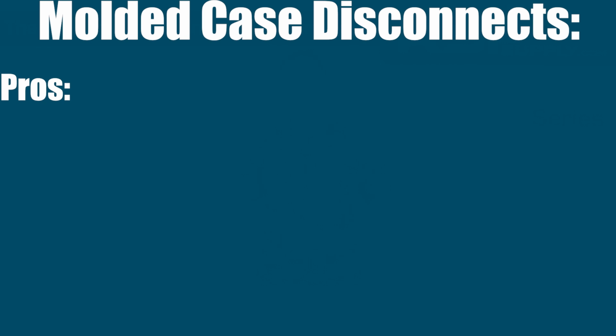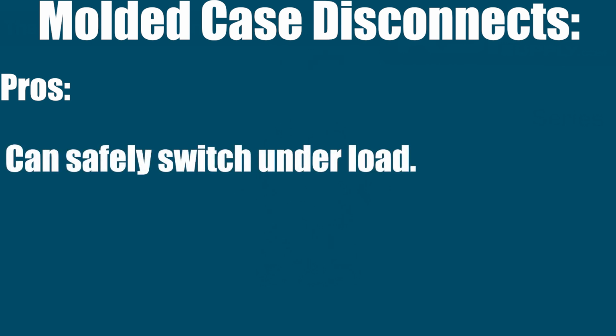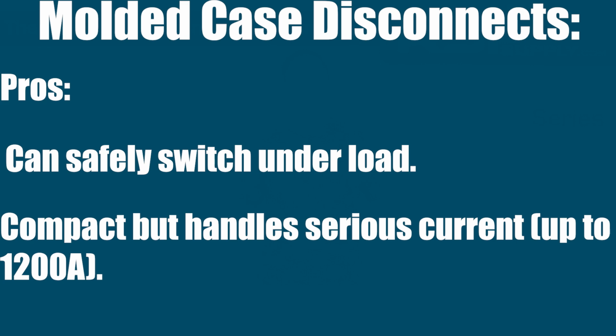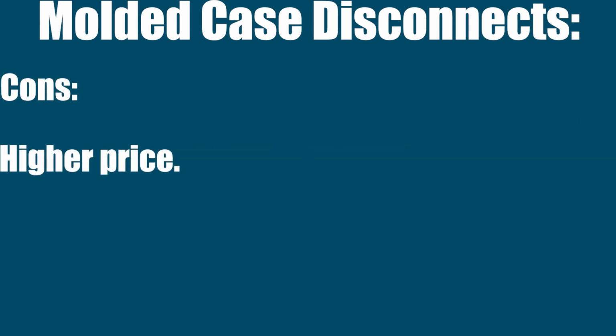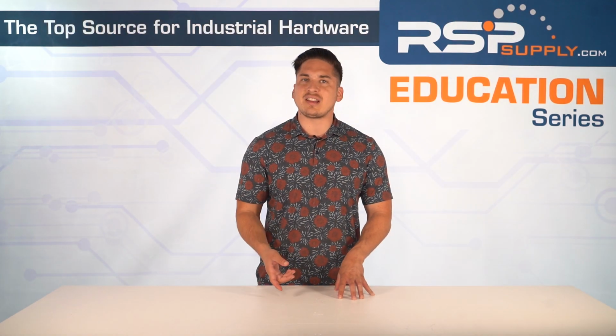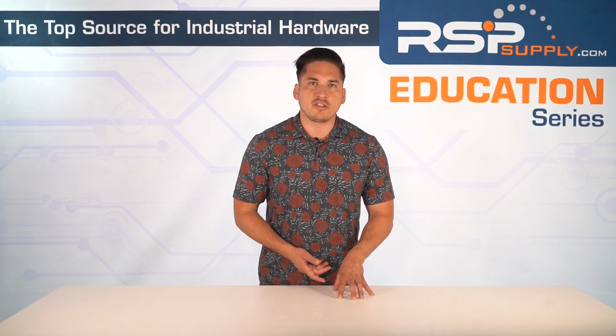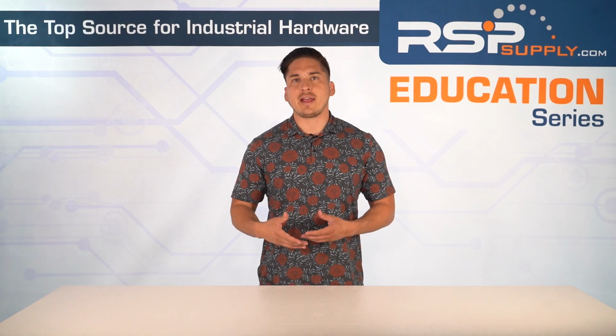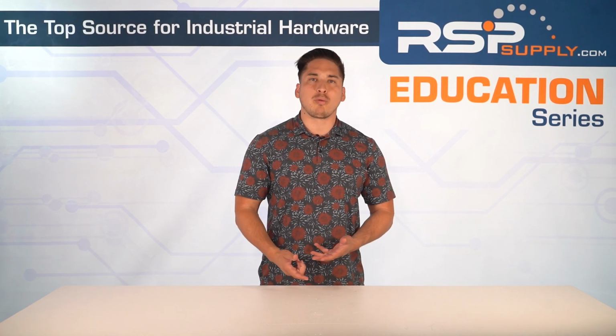Pros of the molded case disconnect: it can safely switch under load. That's a unique feature. Compact but handles serious current up to 1200 amps. Some cons: it does have a higher price. It's best used within data centers or large factories or anywhere where you want switch plus protection, kind of like handling, but without going full breaker.